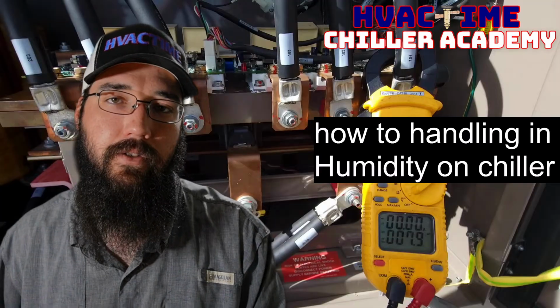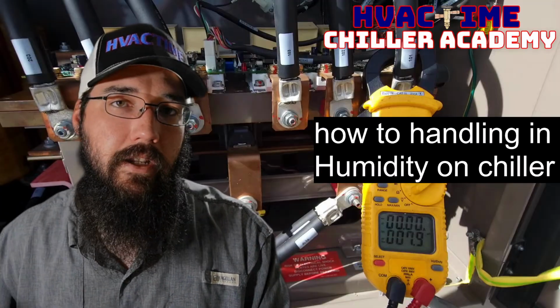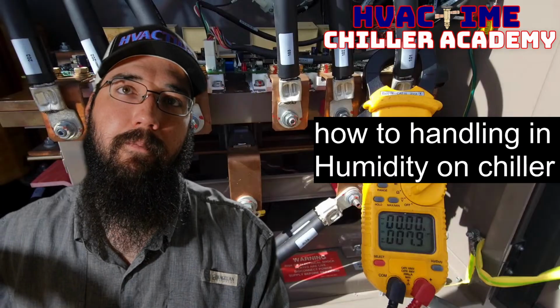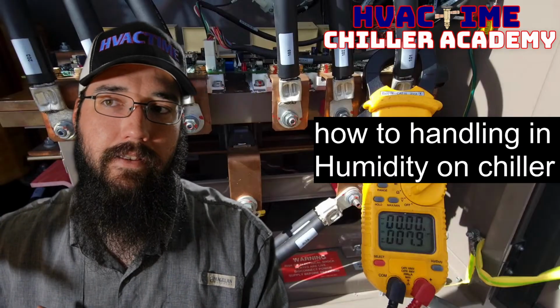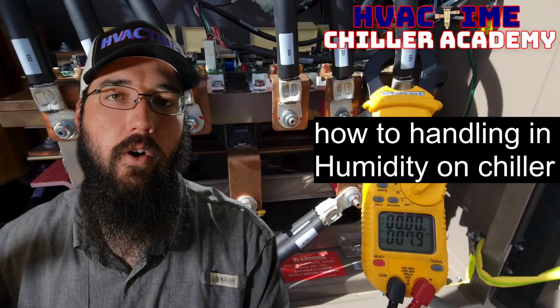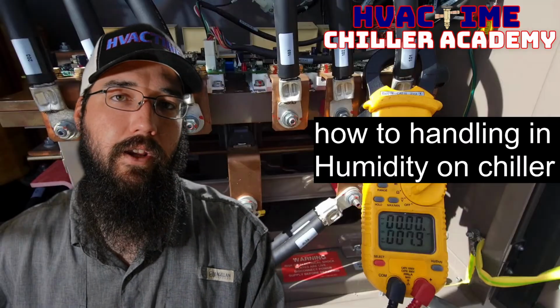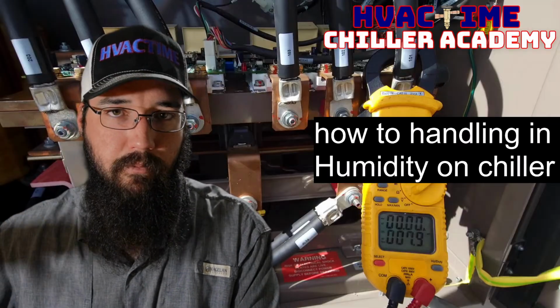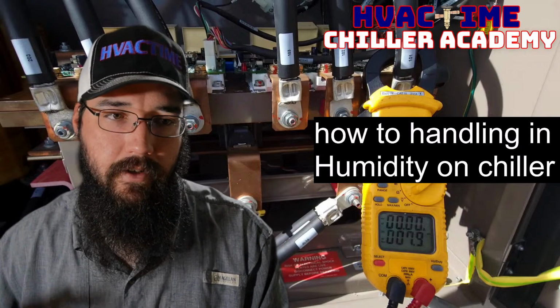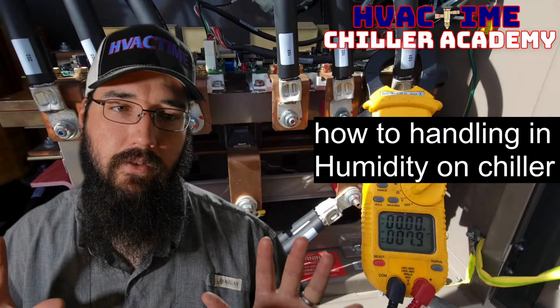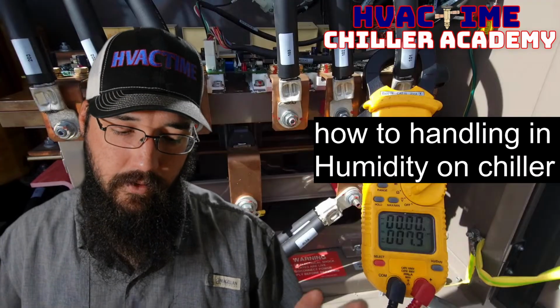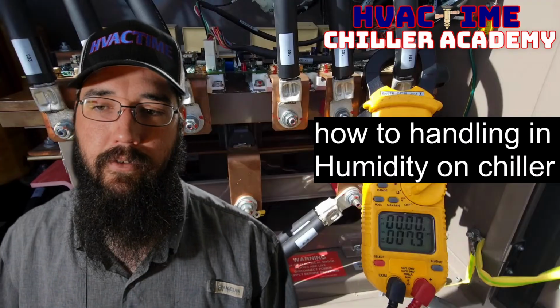Now, you get into corrosion and stuff, but they're not directly affected by humidity at the outdoor system where the coils are. So if you've got a very humid place or environment, that's not going to have an impact on you. So just in case that is not clear for anybody out there, just putting that clarification out.